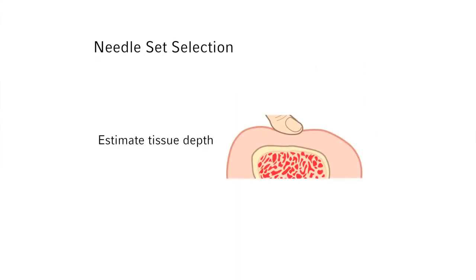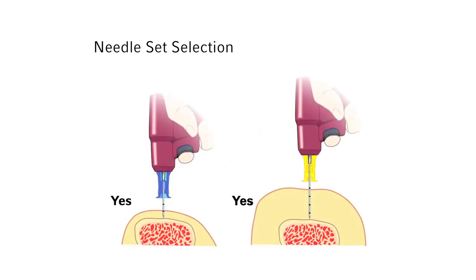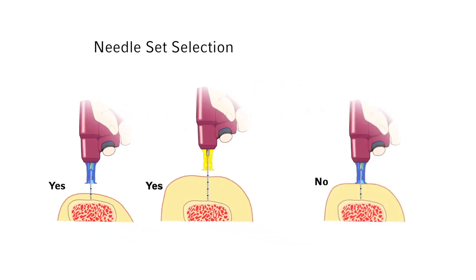Press your thumb or finger over the insertion site to estimate the depth of soft tissue. With the needle set tip touching the bone, the 5 mm mark must be visible above the skin for confirmation of adequate needle set length prior to drilling. If the needle set is inserted through the soft tissue and does not reach the bone, or the 5 mm mark is not visible above the skin with the tip touching the bone, the needle set is too short. A longer needle set or alternate site should be chosen prior to penetration of the bone cortex.